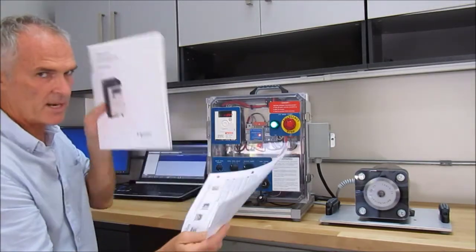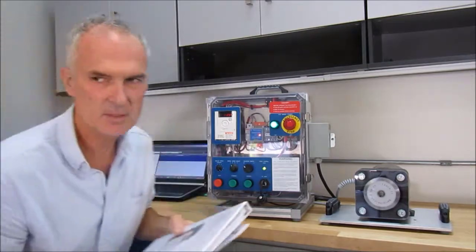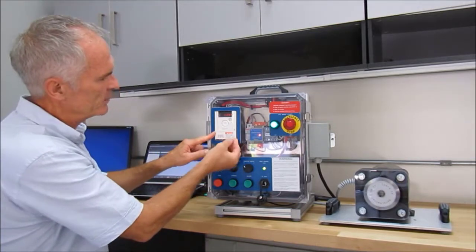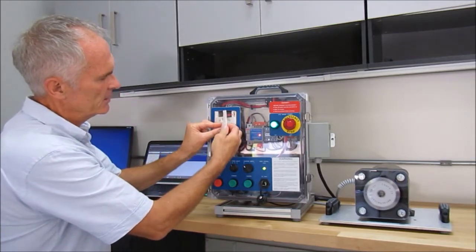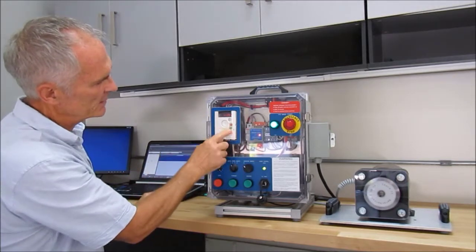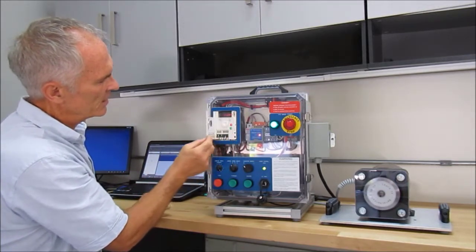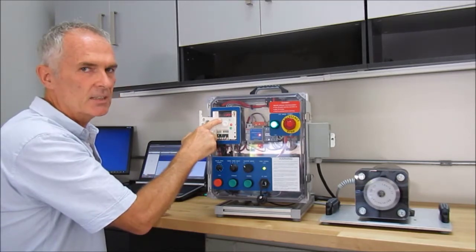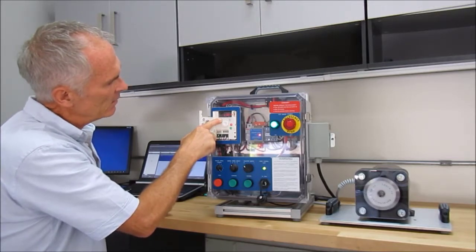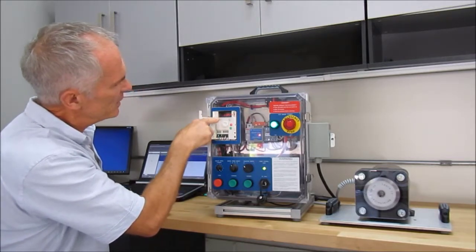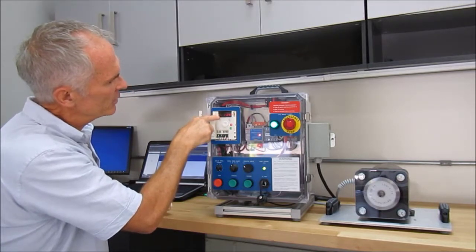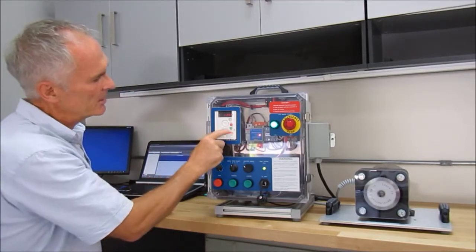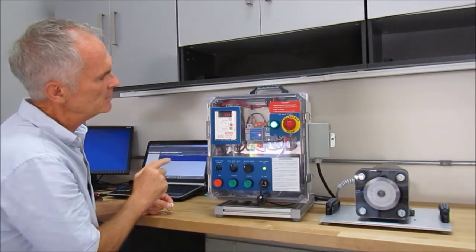So here are your manuals. This is where you'll get the information for setting up your motors. Very important. Okay, now, in order to run it locally, you have to open up this door. Okay, there's a little cover that you can take out that gives you access to the stop and start buttons. You open the cover and there's a mode button. Okay, you hold that mode button for 3 seconds. Okay, now it's going to switch from remote to local, and you're going to see scrolling LEDs on the left hand side, right? It says ready, so it's ready to receive a run command. I'm going to give it a run command, start button, and away it goes.